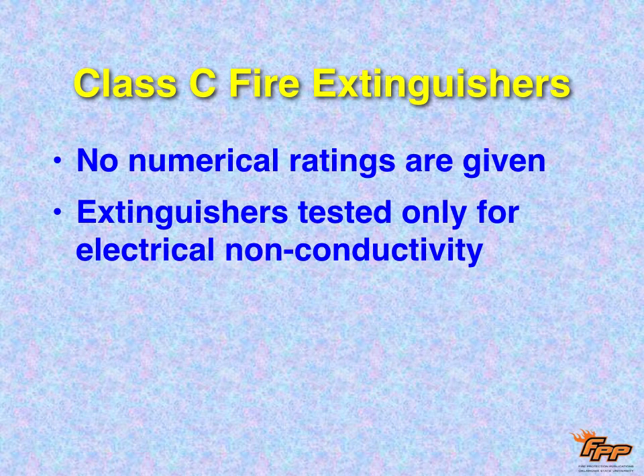For Class C fire extinguishers, there are no numerical ratings, because all we're concerned about here is whether the product is conductive or not. Some of our dry chems are conductive, so you've got to look at it. If it's only an AB extinguisher, don't assume that every dry chem is going to be ABC. Nowadays, most of them are, but some of them are just AB, so don't use an AB extinguisher on a Class C fire. For Class C fires, usually we're going to have CO2 or a dry chem that is ABC.